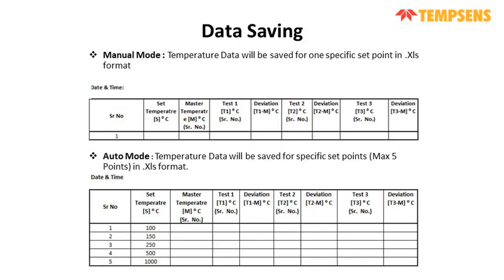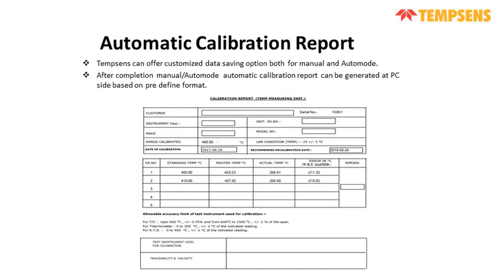It will be saved in such a format: for the AutoCal mode it will have 5 temperatures at a time, and for the manual mode 1 temperature at a time. This type of file will be generated, and the calibration report will be generated. So this is a very user friendly interface, we can say.